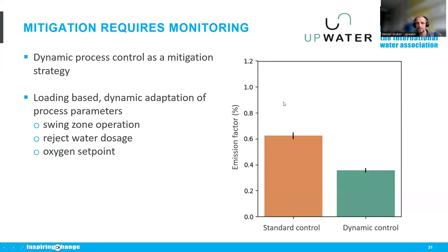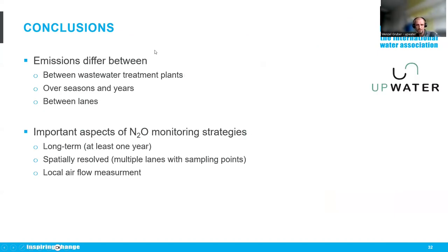From a real wastewater treatment plant with two years of monitoring: with standard control, the emission factor was above 0.6%, and once they implemented dynamic control they reduced it by 50%. This has been shown on multiple wastewater treatment plants. In conclusion, emissions differ between plants, over seasons and years, and between lanes due to spatial variability — so measuring as long as possible makes sense. This is why we need a highly spatially resolved monitoring approach.